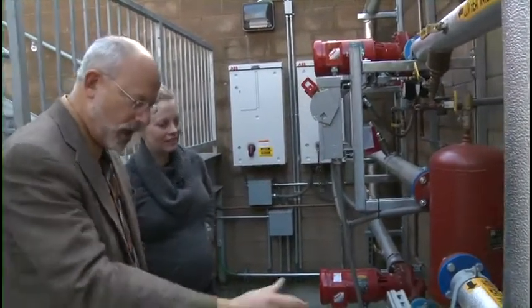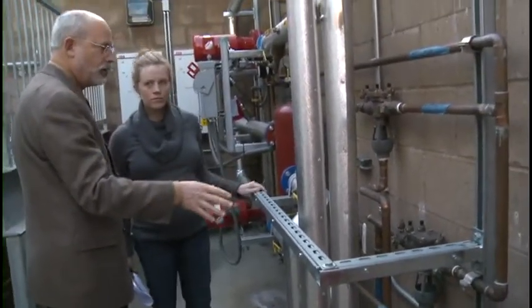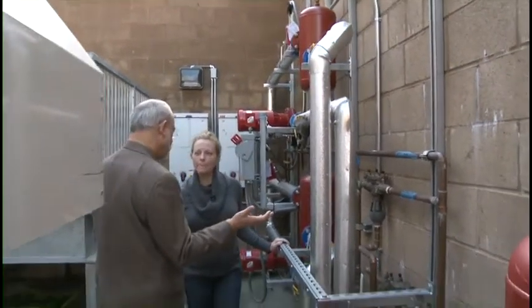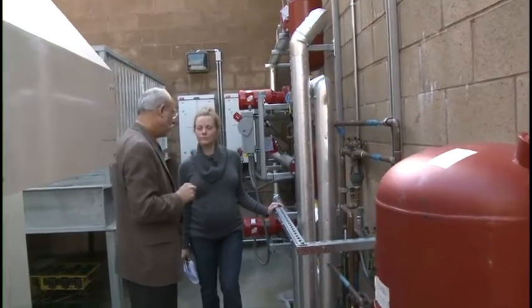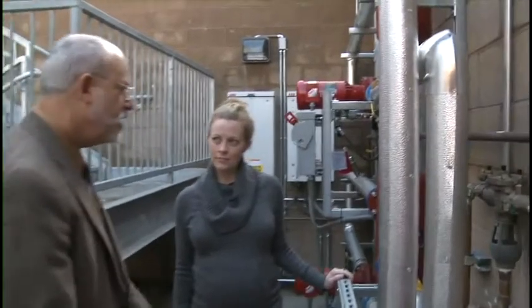Right. Nice. So then the heat comes out of the pumps through these two loops, a high-grade heat loop and a low-grade heat loop, and it goes into the building and is tied into various heating systems within the building. It heats our domestic hot water for two of our large buildings, one 5-story, one 6-story, produces all the domestic hot water, and then it supplements our heating hot water, which runs at about 190 degrees Fahrenheit. So this 250 degree water goes through a heat exchanger, heats up our heating hot water loops, and is circulated through our buildings to provide space heating.